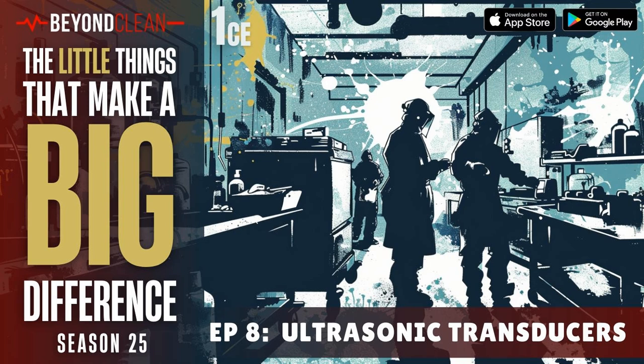Perfect. So ultrasonic cleaners are washing machines that use ultrasonics as the main mechanical form of delivering energy that cleans the instruments. And how it happens is ultrasonic tanks hold the instruments, and those instruments get submerged into water, and the ultrasonic transducers that are bonded to the tanks are emitting ultrasonic energy into that water. And inside of this water, we create a phenomenon called cavitation. Cavitation is when little bubbles that are created by those ultrasonic waves are created and collapse. And when they implode, they release shockwaves, and shockwaves are fantastic to watch, and they are super efficient in removing contamination and debris from instruments. So that's the basic idea.